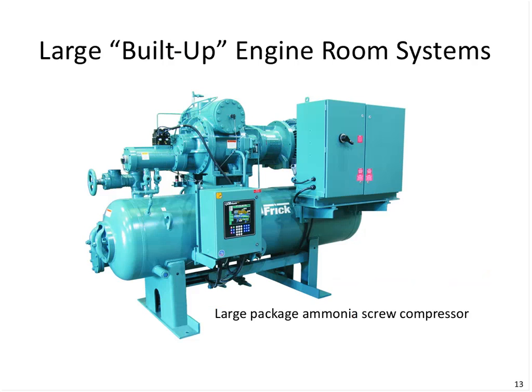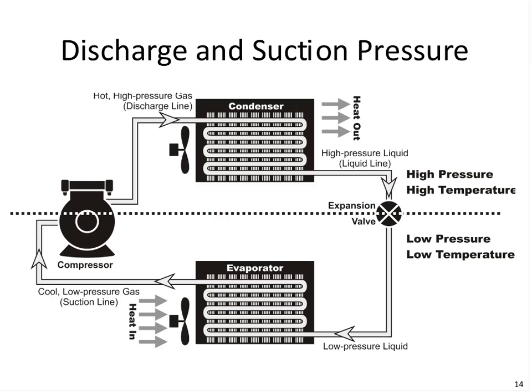Many times these motors are hundreds of horsepower, and we don't want to be turning them on and off repeatedly like a home air conditioner, so they remain rotating. But at the same time, if we don't need the full refrigerating effect, we'll actually adjust this slide valve, which allows the refrigerant to be drawn back into the suction of the compressor. The larger vessel down on the bottom down here is where the oil can separate. The rotors inside the compressor do need lubrication. That's injected right in with the refrigerant, separated out, and then the vapor is pulled from there and discharged to the condenser. This is where the big energy user in these refrigerated systems is.